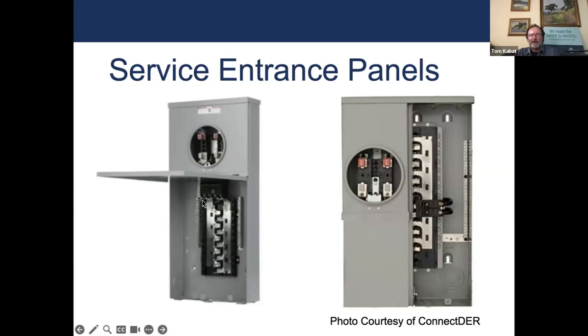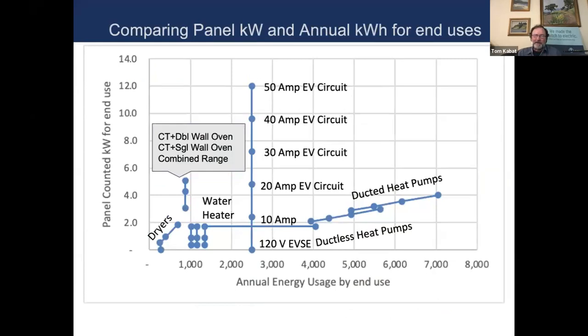That's what these two aluminum bars are, and they have the spaces where the circuit breakers plug on. Usually when you're getting 120 volt power, you're just getting power off of one bus bar. When you're getting 240 volts of power, you've got a breaker that's spanning both bus bars, which are at opposite voltage, and that gives you the full 240 volts. So that's how your panel's able to do that stuff.